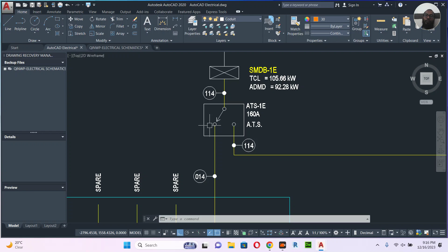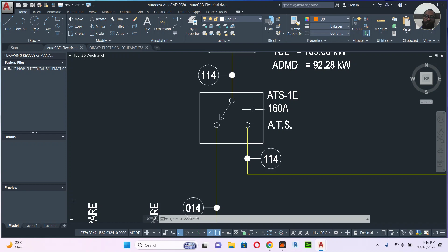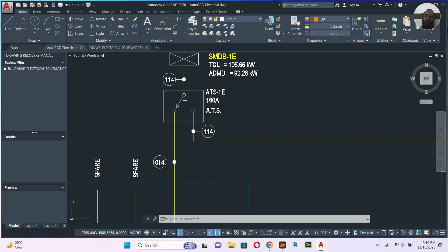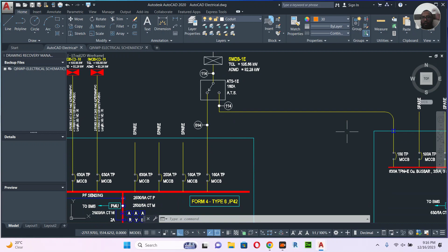So in case of a government power failure, this switch you see here will turn to here. ATS means automatic transfer switch. This is 160 ampere because here we have 160 ampere. If it is 630, it will be 630. The cable you can calculate as I told you in my previous video. In case of power failure, the generator will start and this will change to here, and the power will be given to this SMDB 1E. I hope you understand. Then when the power comes back, it will turn back to here.